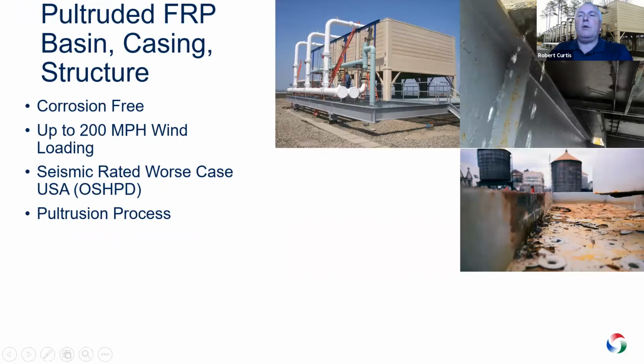And then moving to our next item, which is the pultruded FRP basin, casing, and structure of the tower. We were asked the question, hey, can you design something? Can your cooling tower last longer? We really would prefer it to be more than 5 to 10 or 15 years. And so we looked at the different materials of construction and know that metals will corrode and rust, and decided to go with a completely inert material, which is pultruded FRP. It's completely corrosion free. We designed it for 200-mile-an-hour wind loading, worst-case seismic in the United States. And we're using a process called pultrusion, which allows us to put veils on both sides, 2 smooth surfaces, and to give you also UV inhibitors on the surface to give long life to the product. So that's another area to increase longevity that we answered the question that was asked of us.